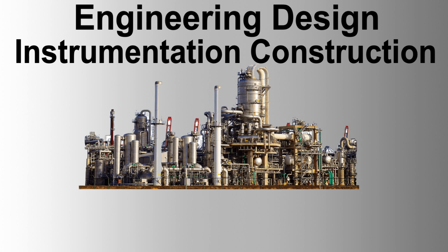Identification shall correspond to the project drawings and cable schedules. Cable termination. Cable terminations shall be made using appropriate connectors and methods specified by the instrument manufacturer. Terminations shall be neat, and connections shall be secure to prevent loose connections and potential signal loss. Cable testing. All cables shall be tested for continuity, insulation resistance, and signal integrity before being connected to the instruments. Test results shall be documented and submitted for approval.